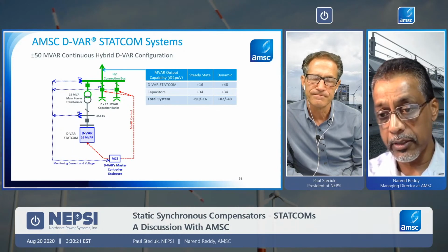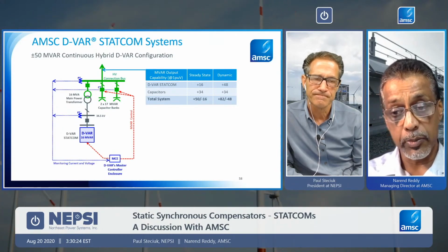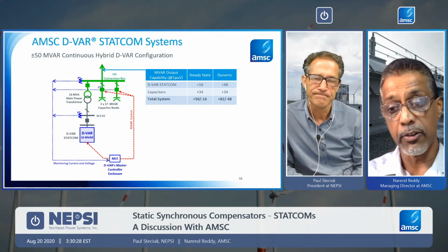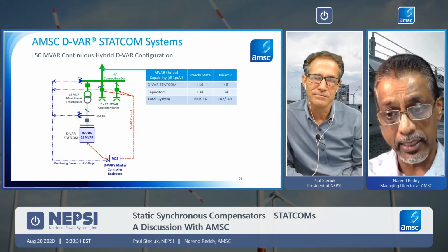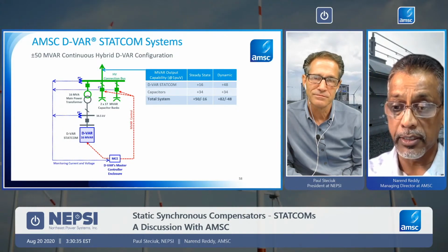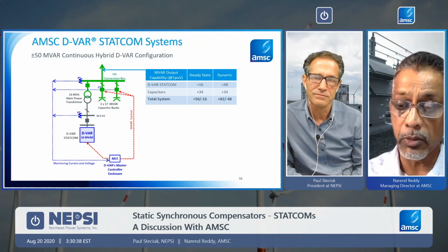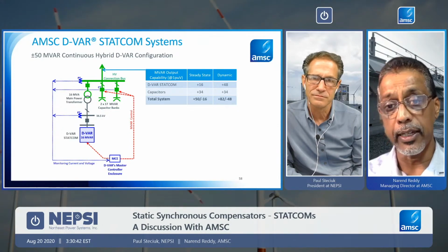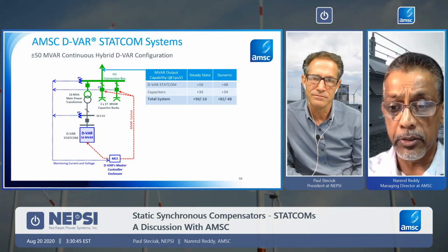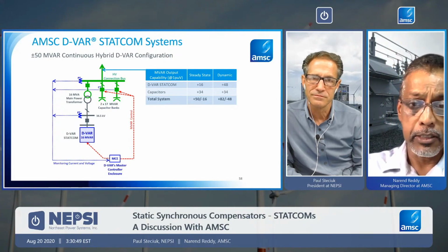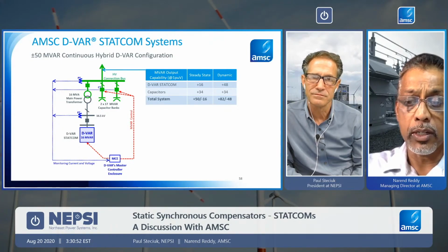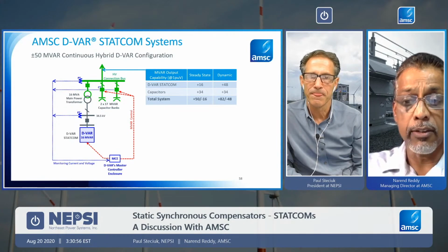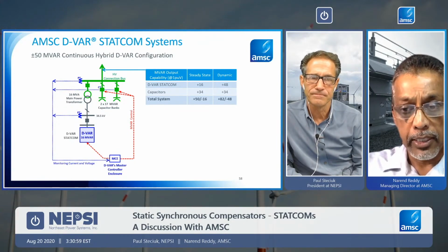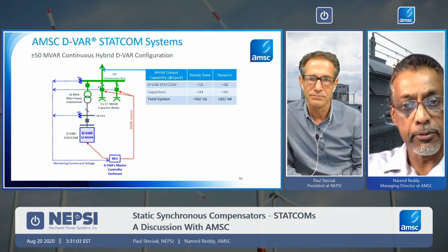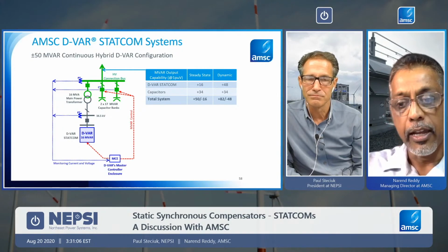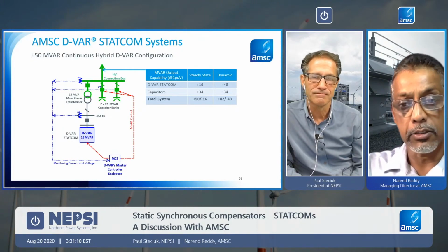And so it meets both aspects. One, it meets the customer's performance requirement. Secondly, the STATCOM, which is really the expensive part of it, is a third of the overall solution. Instead of a 50 megavar STATCOM, you're putting in only a 16 megavar STATCOM. If you look at the cost savings, it actually flows down into the installation, the substation, all the way through. You will see the benefit of doing that. And the other neat point about hybrid solutions that we do is the capacitor or passive device sizes are selected in such a way that we could use the DVAR to provide the soft switching capability. So really, from a performance standpoint, it is a fully dynamically variable 50 megavar capacity at the point of connection. But internally, you are leveraging different technologies to do that.